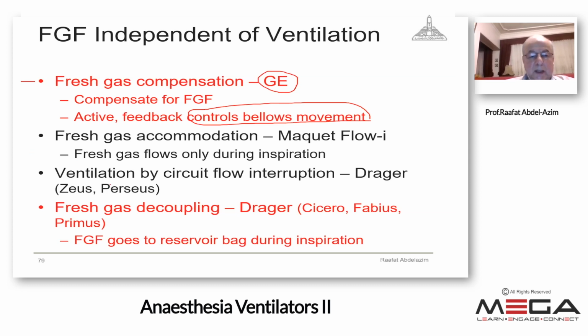That's fresh gas accommodation. In Draeger ventilators, Zeus and Perseus, they have what is called ventilation by circuit flow interruption. And in Draeger Cicero, Fabius, and Primus, we have fresh gas decoupling, and I will describe it in detail. So we have different mechanisms according to the manufacturers to stop the addition to the tidal volume, to stop augmentation of the tidal volume and the occurrence of barotrauma. I put these two in red because these types of ventilators are available in Egypt. So I will describe them in more detail.